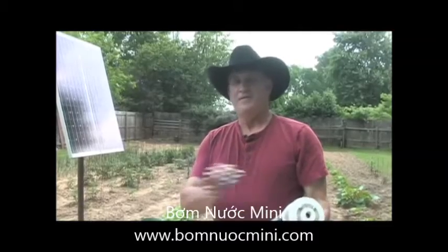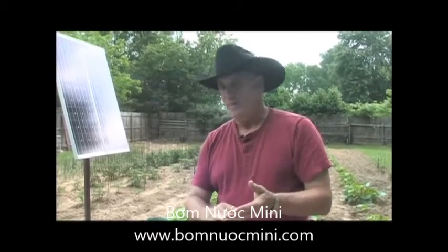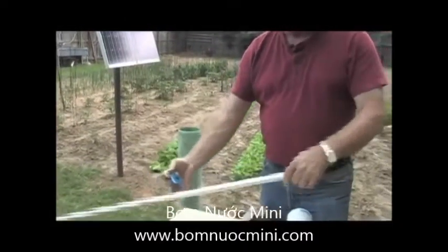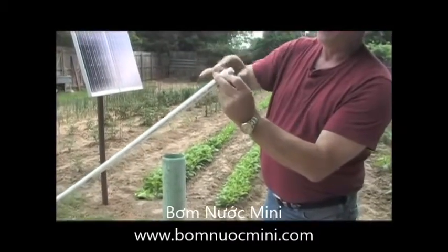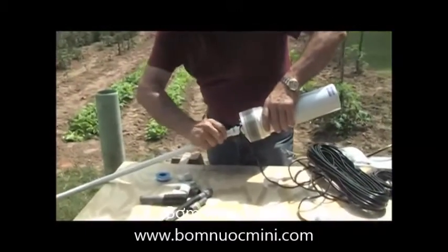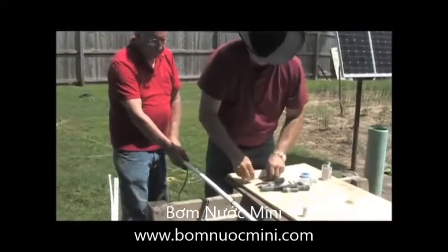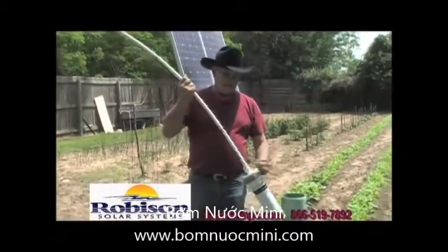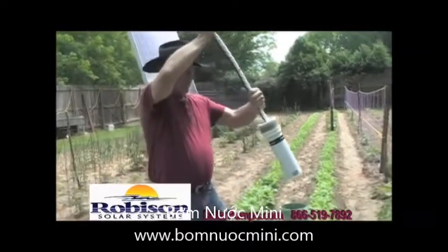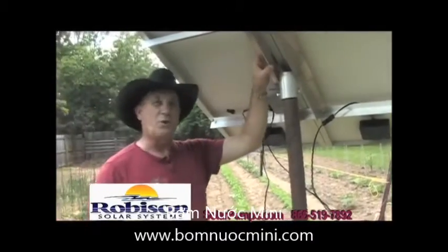One thing I like about the Robison Solar System is that everything is complete and already done except for your pipe and fittings, because they don't know how far each well is or how far your power source will be. I'm using white PVC pipe — put a fitting on it, add a little Teflon to make the connections better, and screw it right into the top of the submersible pump. Put a zip tie about every three or four feet. Now we've got the pump on the PVC pipe with the wire zip-tied all the way up, and we're going to insert it into the casing all the way down to our mark.